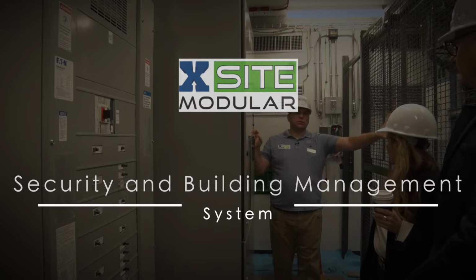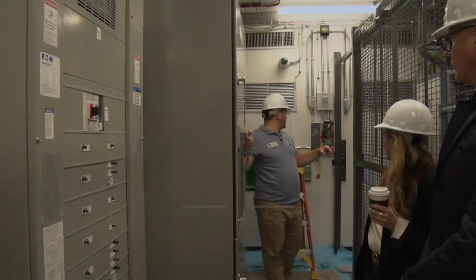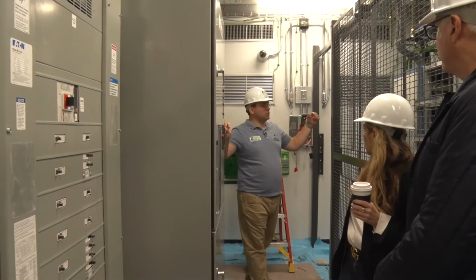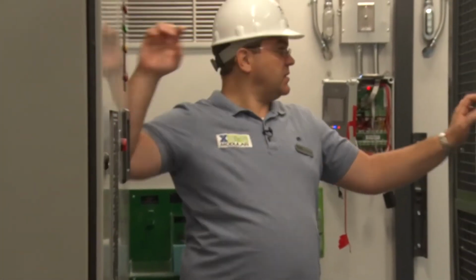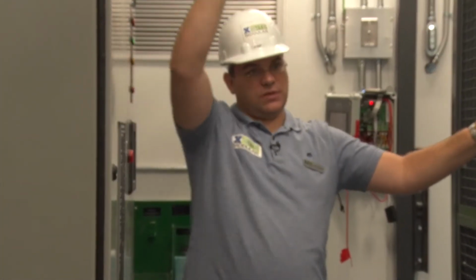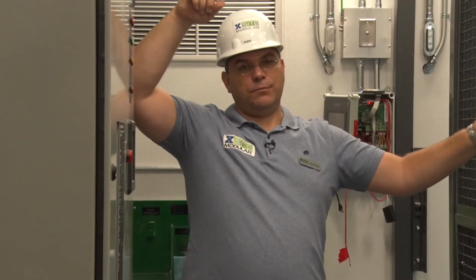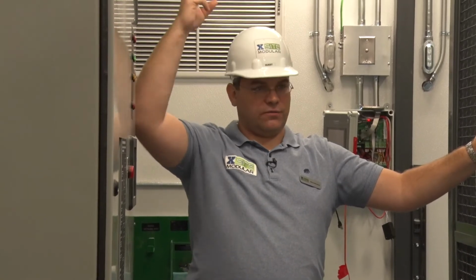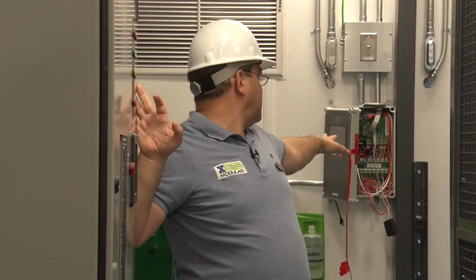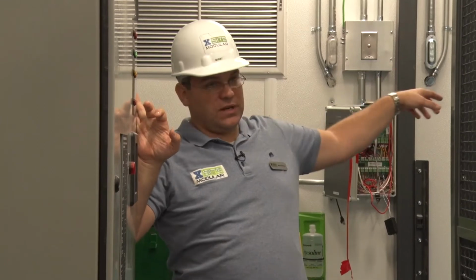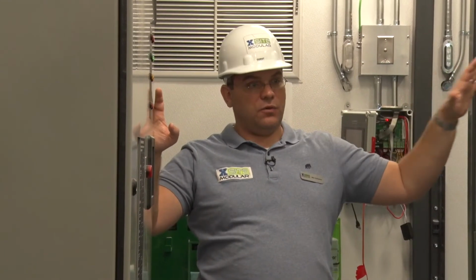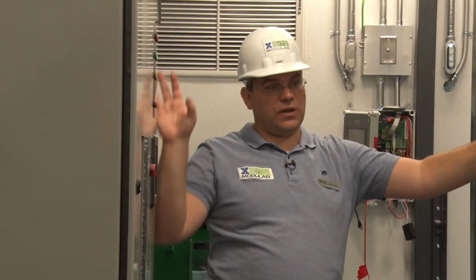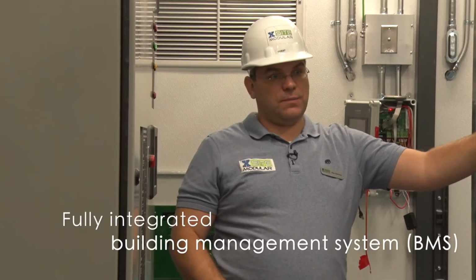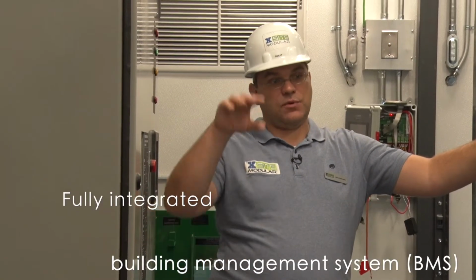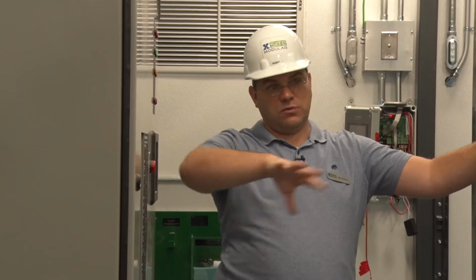All the devices we use are included in the base price of our building, including the BMS, which communicates with all the different devices—the DC plant, the ATS, the generators, the UPSs, and pretty much all the temperature, humidity, and differential pressure sensors—everything comes back to these three HVAC controllers, which pick up everything and communicate. So if a client never wanted to do a single thing else, they'd have a fully integrated BMS where they could look at all the cameras, access control, motion sensors—everything monitored.